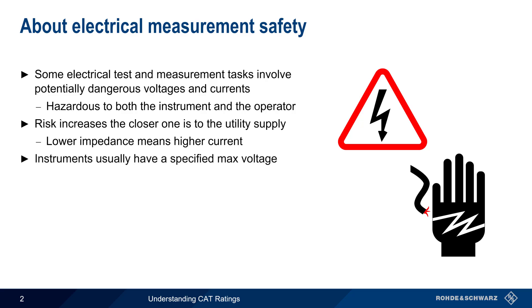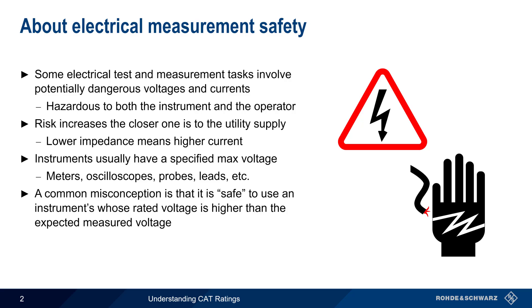Test and measurement instruments normally have a specified maximum input voltage, and this applies not just to multimeters and oscilloscopes, but also to the leads and probes used with these instruments. A very common misconception is that it's safe to use an instrument when the instrument's rated voltage is higher than the expected measured voltage. One reason why this assumption is dangerous is that it ignores the possibility of something called transients.